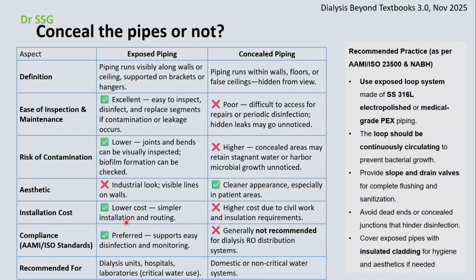If you have to conceal it, you have to use removable panels. Yeah, removable panels are also good, but then people become complacent and daily checking doesn't occur. If it is a visible pipe, then we can inspect it daily. Also, it's easy access, and any leak can be addressed simultaneously. If it is concealed, even with panels, then we are not able to identify minor leaks, and they may erode the surfaces inside. Architects would want to conceal. Engineers and we would want not to conceal, and we have to be the referee there.